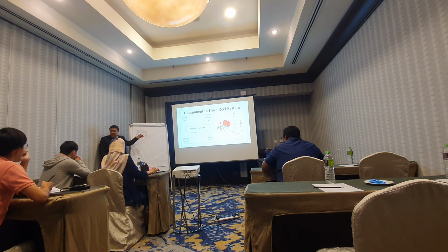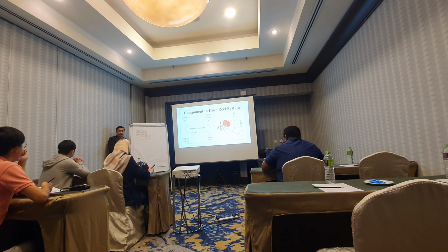So it is a combined tank. Memang combined, you see it combined, but internally it's not combined. You need to separate both tanks. Sebab apa? Because for sprinkler system, dia ada filling rate dia sendiri. Maksudnya air yang masuk tu berbeza dengan hose reel. Kadar air masuk. So you punya question tadi, there are people doing like this, yes, it is acceptable by Bomba and permittable by the law. Cuma you need to have the separator lah.